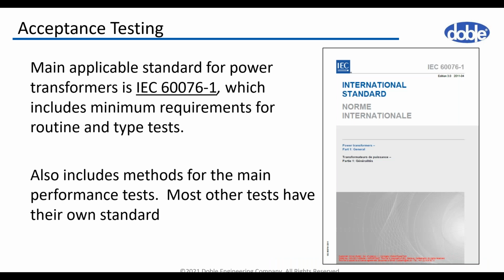I already mentioned that applicable standards should be used, and IEC 60076 Part 1 is the standard for power transformers, where you can find the minimum requirements for routine and type tests. This standard includes methods for some of the performance tests, and some of the other tests have their own standards.